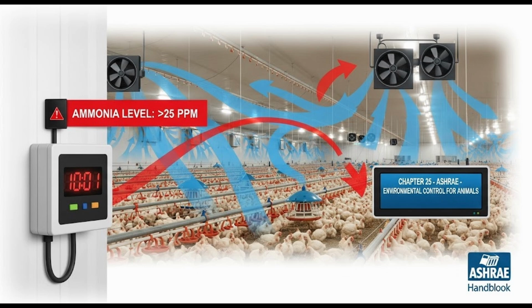Okay, like balancing a checkbook for heat. Exactly. You need good data, like how much heat different animals produce. The ASHRAE Handbook Fundamentals volume has tables for that. Then you pick your target indoor temperature based on the species. Which the handbook provides examples for too, right? It does. And you use the outdoor design temperature for your climate.